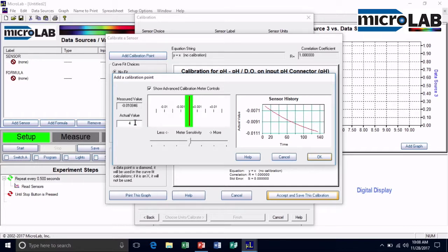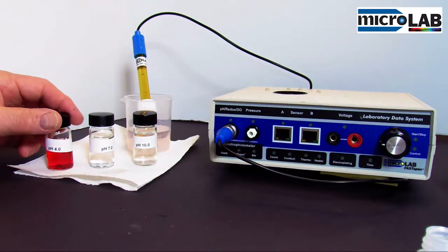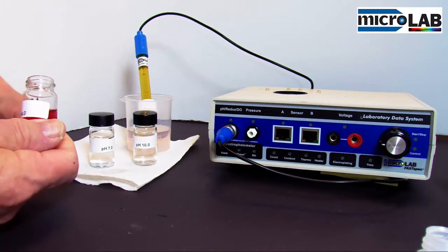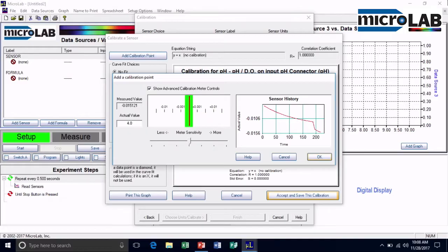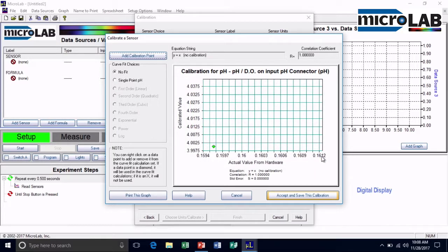I'm going to start with a 4.0 pH. And if we can switch over here, I've got that in a vial, and I'll take the top off, take the sensor, and as I put this in, you're going to see the sensor react. And it switched way high, and now it's kind of stabilizing. I'll stir it around a little bit. And you can see in the center, the green equilibrium display is stable, and the graph is pretty stable at this point. So what I've got right now is the number coming out of the sensor for pH 4. So I'm going to say, okay, I'm going to grab that point, and we got it.